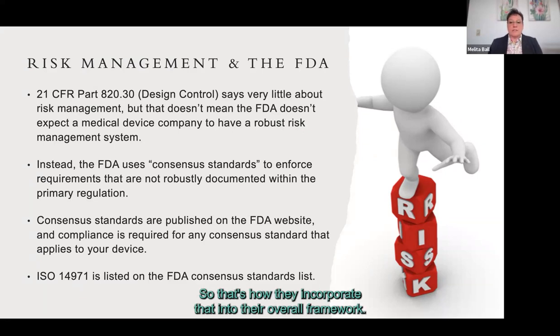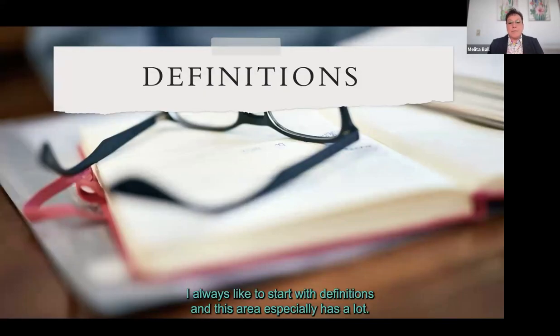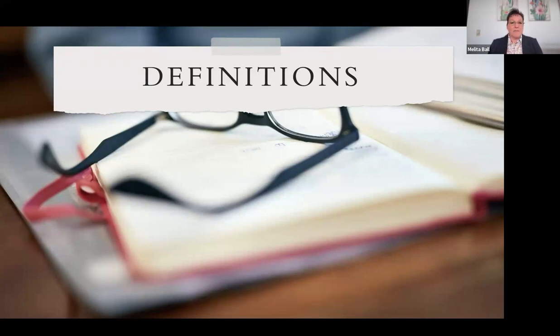That is exactly what happened for risk management. The FDA points to ISO 14971, the most recent release being 2019, which is part of that FDA consensus standards list. That's how they incorporate it into their overall regulatory framework.